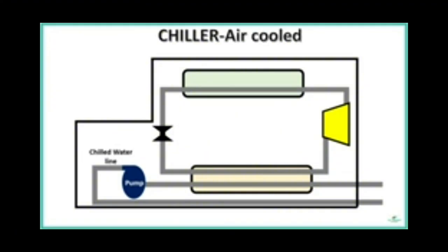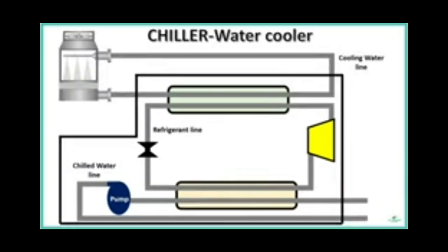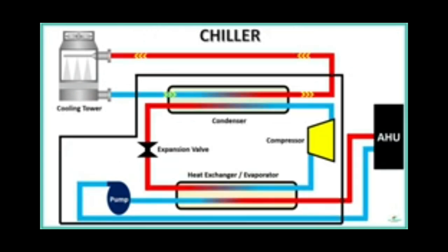In an air-cooled chiller, the refrigerant flowing through the condenser is cooled by atmospheric air. In the case of a water-cooled chiller, the refrigerant is cooled with the help of cooling water from the cooling tower. During operation, the cooling water flows from the cooling tower to cool the refrigerant at the condenser and is circulated back to the cooling tower. The refrigerant in the refrigerant line is compressed by the compressor and sent to the condenser at high pressure. At the condenser, the refrigerant is cooled by cooling water and passed through the expansion valve to reduce the pressure.